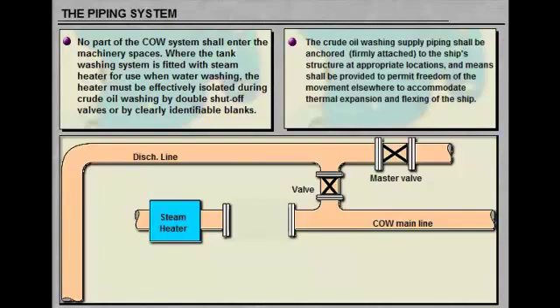The crude oil washing supply piping shall be anchored to the ship's structure at appropriate locations and means shall be provided to permit freedom of the movement elsewhere to accommodate thermal expansion and flexing of the ship.